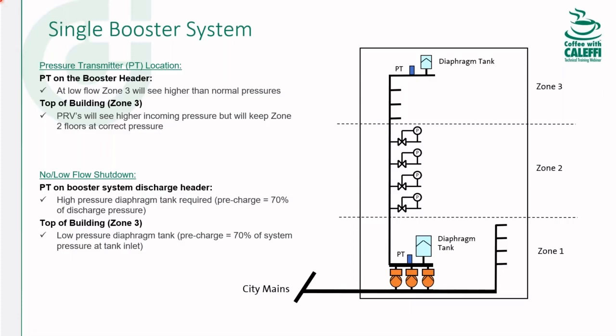Any booster system you see out there that doesn't have a diaphragm tank for low flow shutdown requires a zero flow condition for a set period of time for it to shut down. I also recommend to you designers out there that if you specify a booster system, make sure the manufacturer has a controller that's capable of going from a roof sensor to a discharge manifold sensor fairly easily, without somebody getting on an airplane flying out there with some special software. Make sure the controller has the capability to easily switch from one to the other.